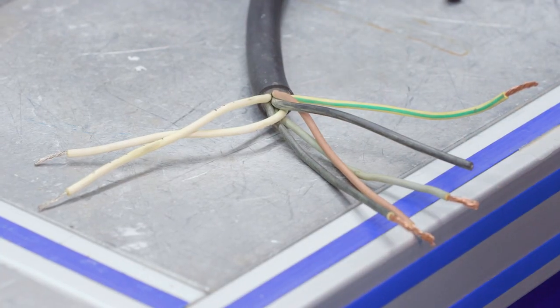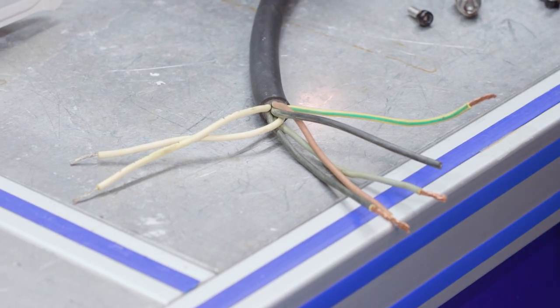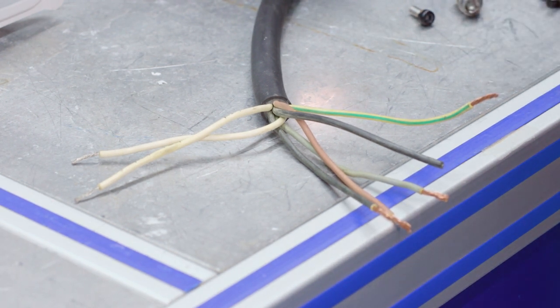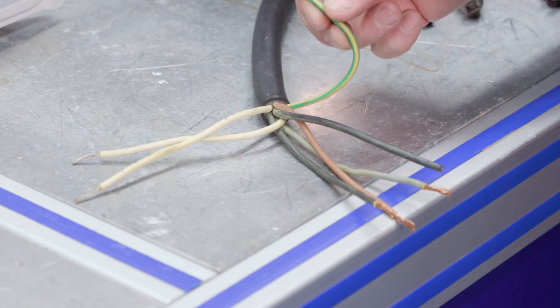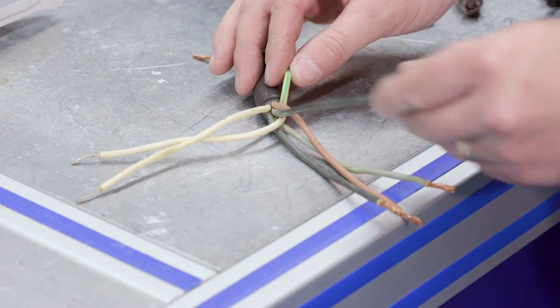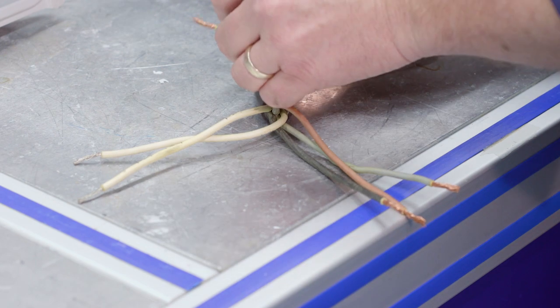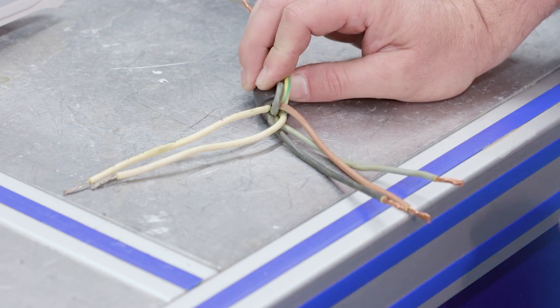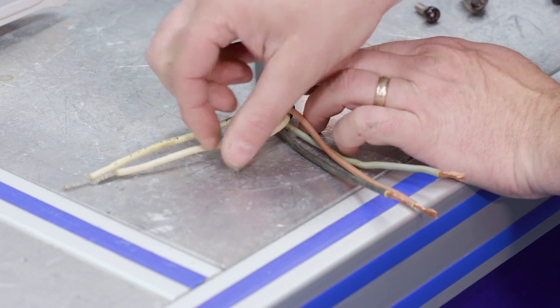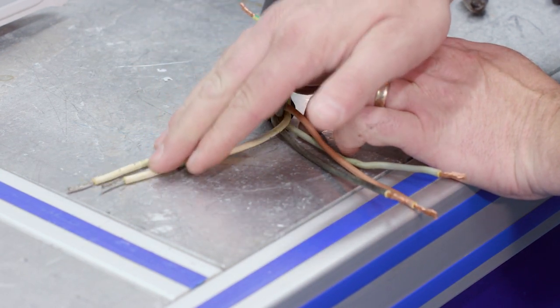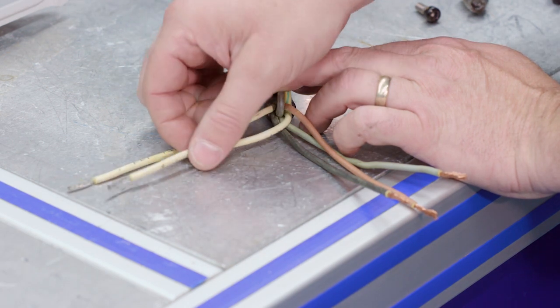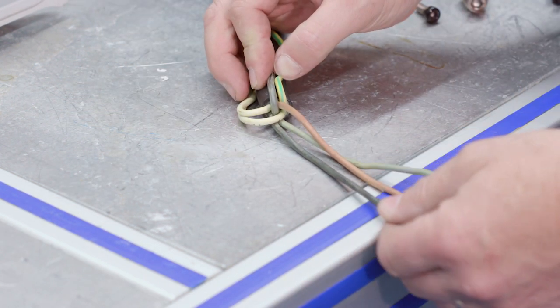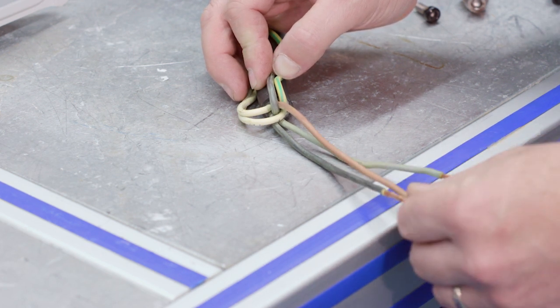Here's the power cord, or at least part of the power cord, that we just need to talk about and identify what cable is what. Let's start one at a time. We can tell this is my ground. This cable back here is not used, so we don't have to worry about that. That leaves us with five leads. You can tell here there's a T1 and a T2, so those are my sensors. I don't at this point in time really know which one's leak detection and which one is thermal, but I know those are for my sensors. That leaves us with three power cables.